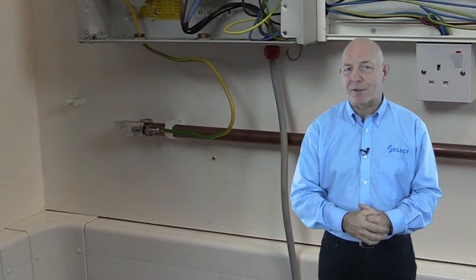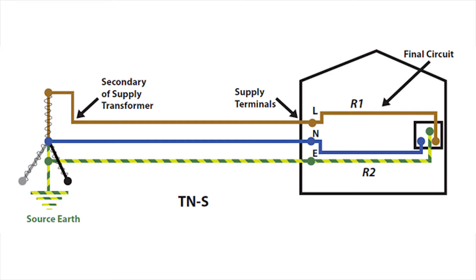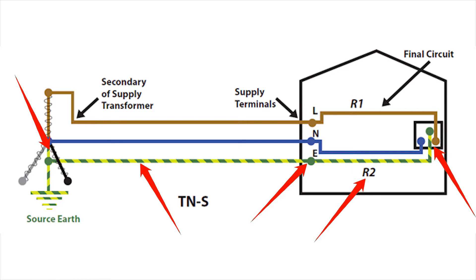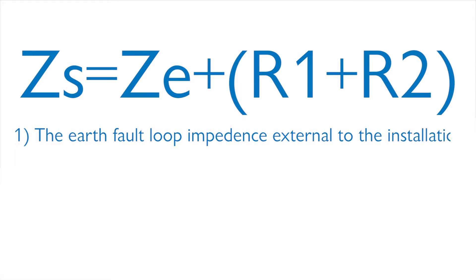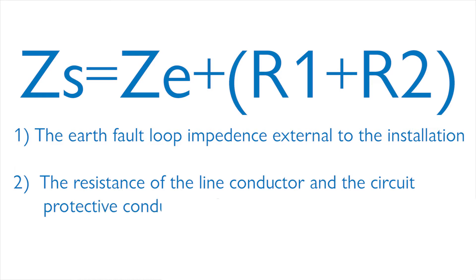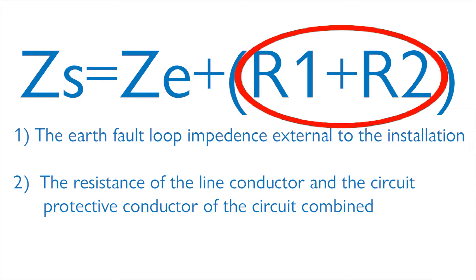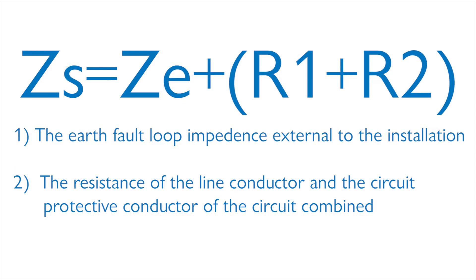The earth fault loop impedance comprises the point of a fault, the circuit protective conductor, the consumer's earth terminal and earthing conductor. For TN earthing systems, this also includes the metallic return path provided within the distributor's supply cable, the path through the earth neutral point of the distributor's transformer, the transformer winding, and the line conductor from the transformer to the point of the fault. The earth fault loop impedance comprises two parts: one, the earth fault loop impedance external to the installation, known as ZE; and secondly, the resistance of the line conductor and the resistance of the circuit protective conductor combined, R1 plus R2. The earth fault loop impedance can therefore be calculated using the formula ZS = ZE + R1 + R2.